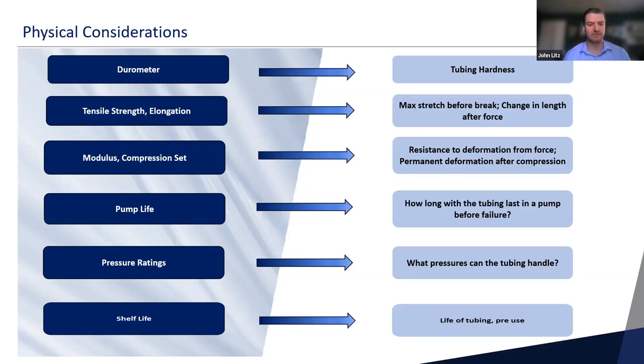And lastly, shelf life. Shelf life is just the life of the tubing pre-use, and that can include both gamma irradiation shelf life or your standard shelf life. In most cases, from what I've seen in the industry, you're going to see a shelf life on silicone tubing of anywhere from 3 to 10 years, with the general average being around 5. Post gamma, more likely you're going to see a shelf life of 2 to 3 years.